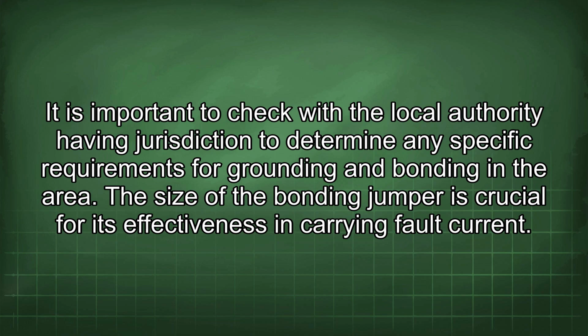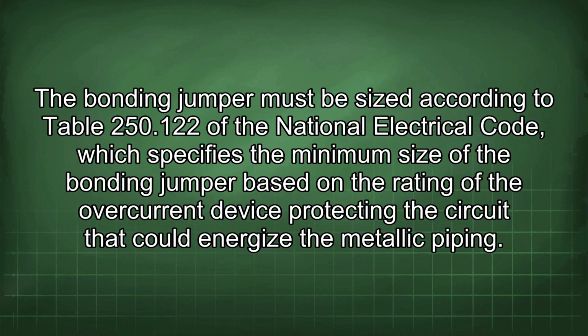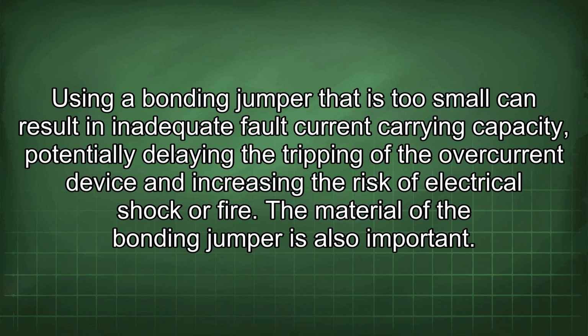The size of the bonding jumper is crucial for its effectiveness in carrying fault current. The bonding jumper must be sized according to Table 250.122 of the National Electrical Code, which specifies the minimum size of the bonding jumper based on the rating of the overcurrent device protecting the circuit that could energize the metallic piping. Using a bonding jumper that is too small can result in inadequate fault current carrying capacity, potentially delaying the tripping of the overcurrent device and increasing the risk of electrical shock or fire.